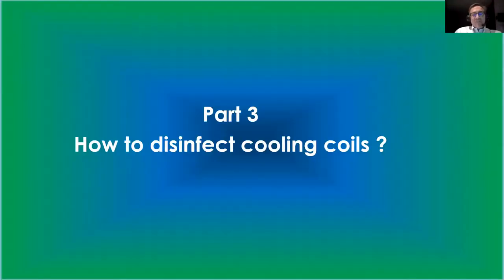In part three, I'll get into how we disinfect a cooling coil. If you remember, when we're dealing with coils, it's a non-moving object. We're shining a UV light on it and there is no movement. So we have plenty of time. Remember, the dose is the intensity multiplied by time. For cooling coils, we have lots of time.